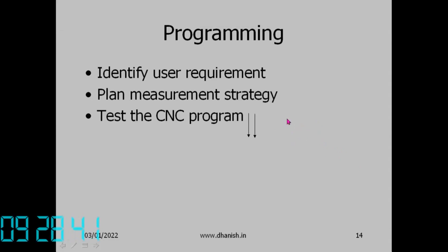For programming, the steps are: identify user requirements including allowable measurement uncertainty; plan the measurement strategy including number and distribution of points, work holding, and other parameters; then test and verify the CNC program. If it is a one-time measurement, the program is run directly; for repeated measurements, the program is stored. Modern CMM software also has simulation capability similar to CNC machining simulation.